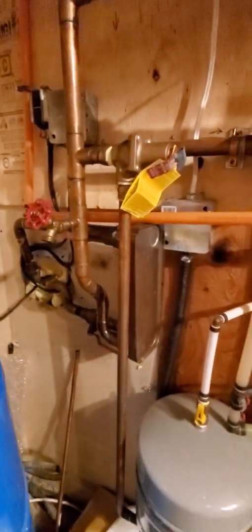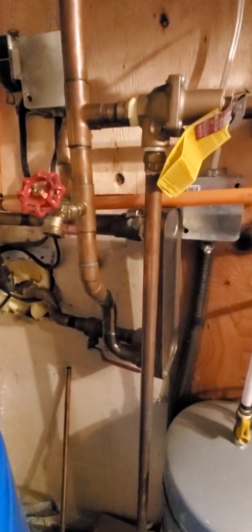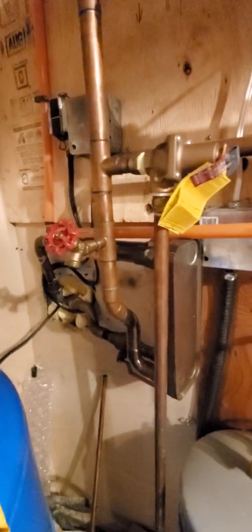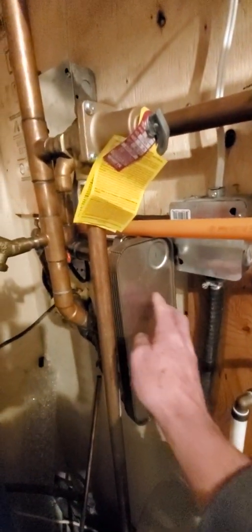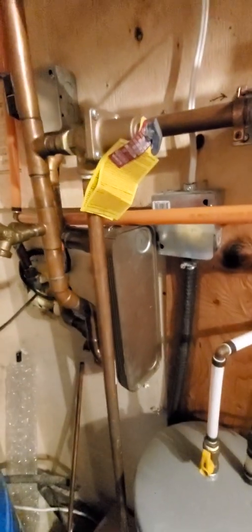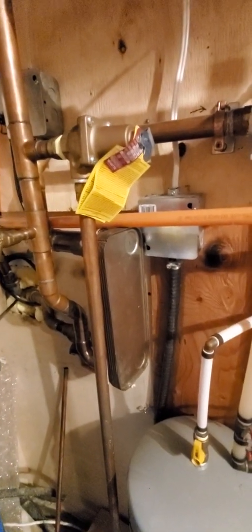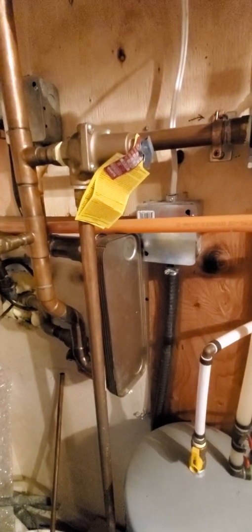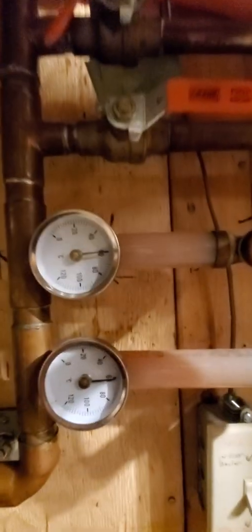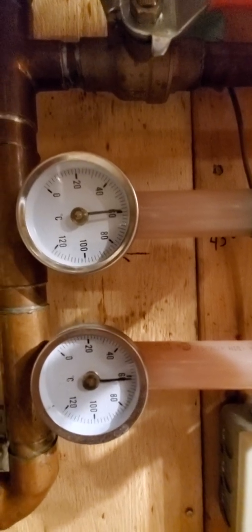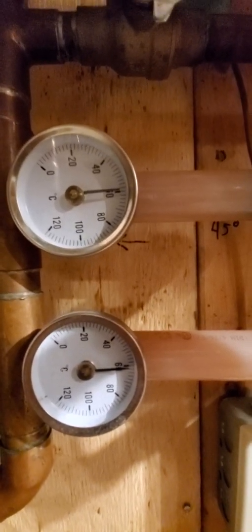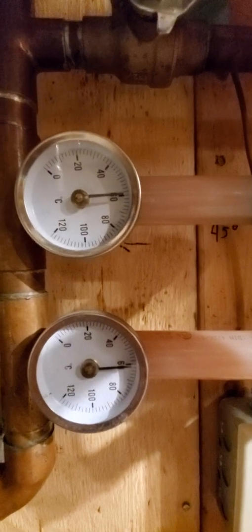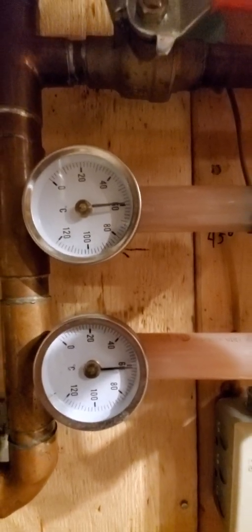So remember up top at the back of the boiler you had a green pump and a red pump. Well, the green pump feeds this system right here, and it comes into this heat exchanger right here. Some people call it heat plate. And basically it just transfers the heat from that hot glycol into the next system. As you can see right now, it's kicking pretty good. This is 60 degrees Celsius. So yeah, it's really hot, functioning properly.